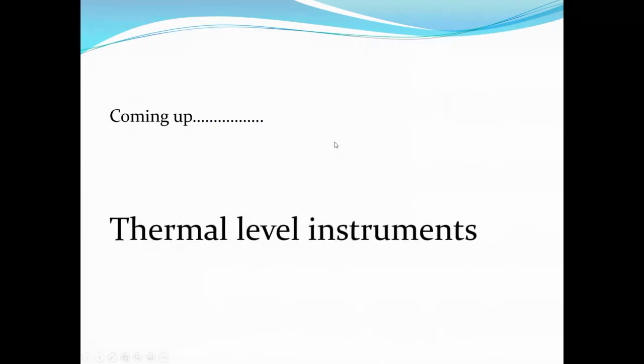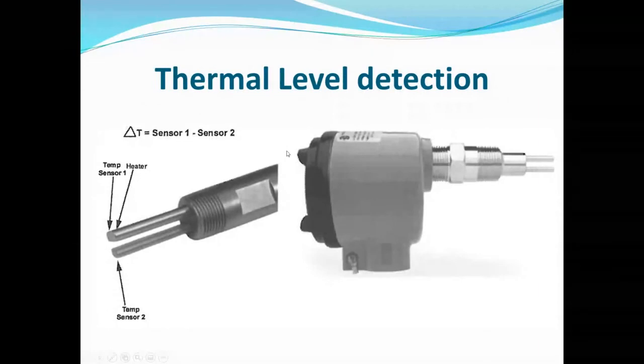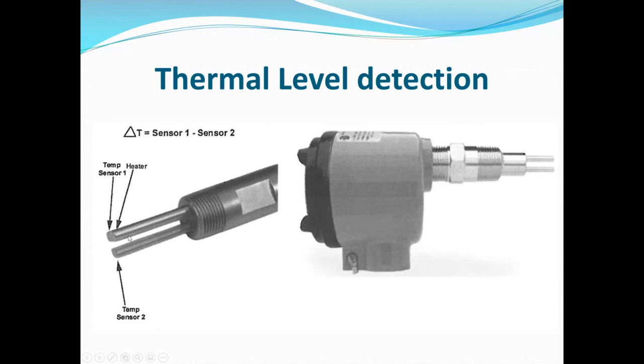Moving on to thermal dispersion — very simple, much more straightforward. The thermal level detector has two probes: one is essentially heated and both have sensors. They either keep the two probes at the same temperature and detect a difference, or vice versa. These are almost exclusively point level devices. The change in temperature is the temperature sensed by the heated probe minus the temperature of the unheated reference probe. When not covered by anything, temperatures differ considerably; when covered by a process medium, temperatures are closer together — that's the science of it.